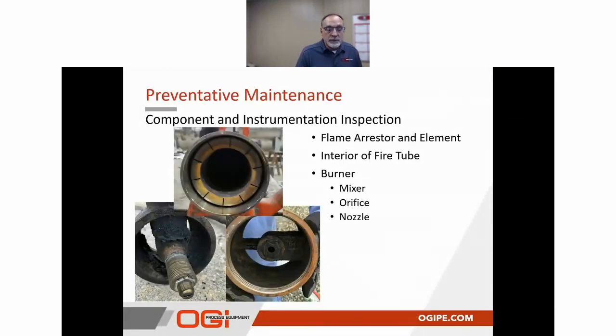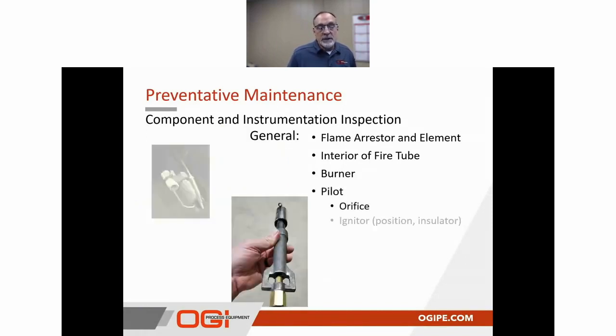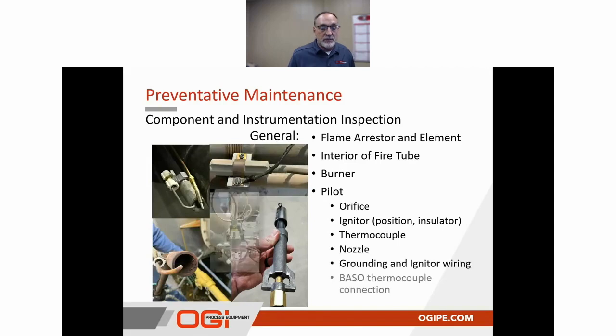We want to confirm that the mixer and the orifice and the nozzle are clean, that there's no soot or buildup on that, and obviously if they're dirty, they'll actually create a poor combustion because they're not going to be entraining air properly with the fuel that we're trying to burn in the fire tube. And then obviously the next step is to take a look at the pilot.